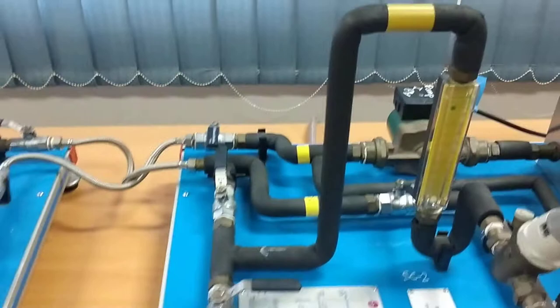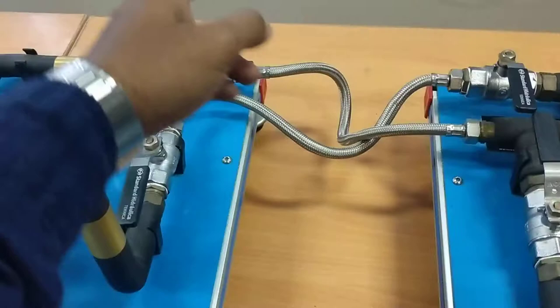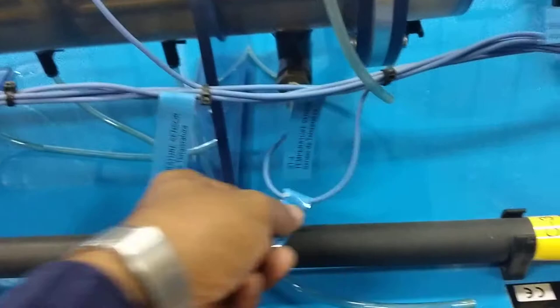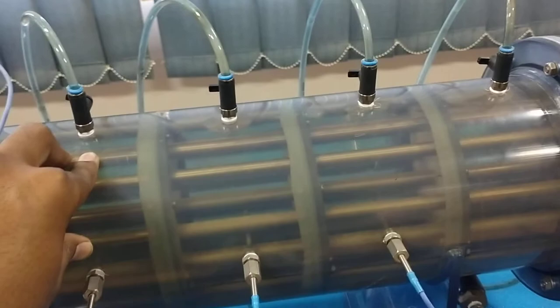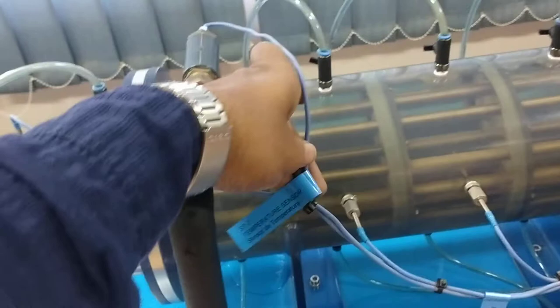Okay. The cold water will move from this point, this valve, flowing through C2. This is the C2 pipe, entering through the bottom of the heat exchanger. There is a temperature sensor ST3 before the cold water moves through the shell of the heat exchanger. The hot water moves in the tubes while the cold water moves in the shell, exiting from this point, where there is the temperature sensor ST7. So ST3 is the inlet temperature of the cold water, and ST7 is the outlet temperature.